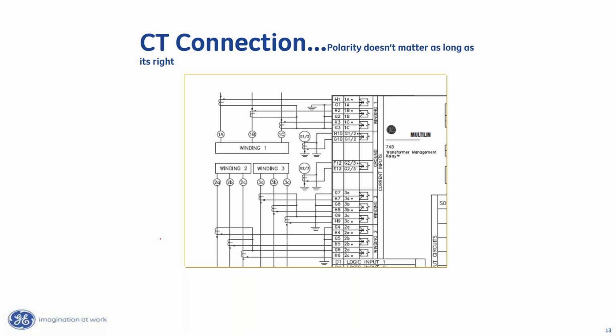What I mean by that is a lot of times people think there's something magical about this little dot on the CT. There's nothing magical about the little dot on the CT. All that little dot represents to us is which side of that CT is the H1 terminal and which side is the X1 terminal. So if we look at this one right here, that's the H1 terminal, that's the X1 terminal. Now, typically, CTs are installed by the equipment manufacturer. The equipment manufacturer always puts the polarity dot away from their equipment.